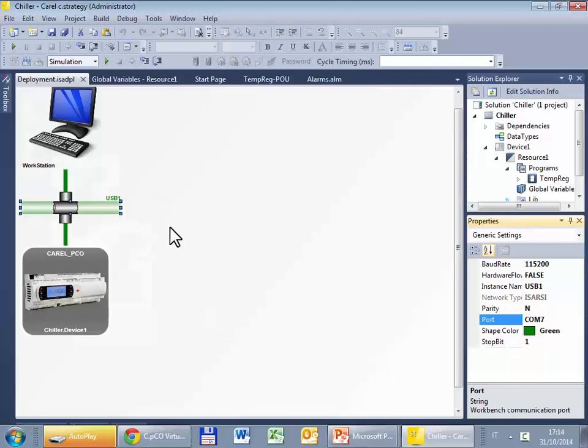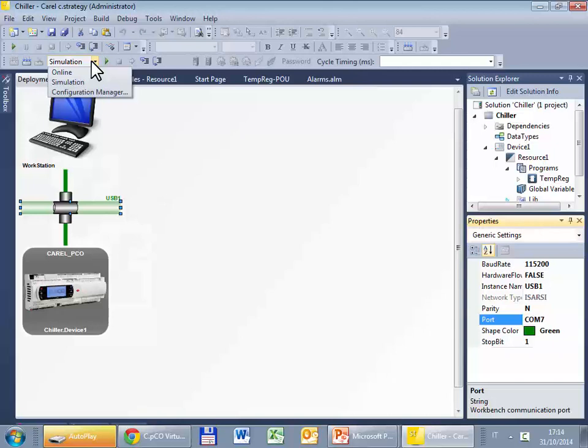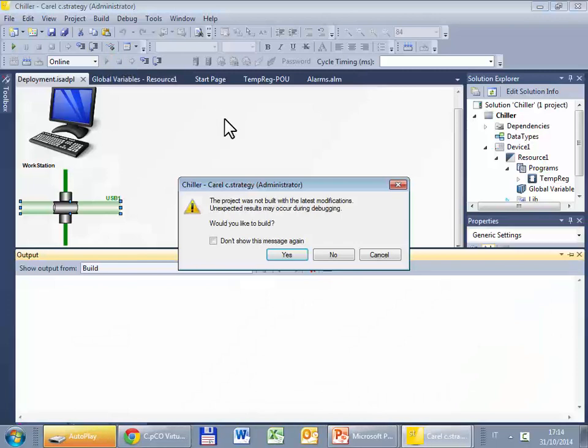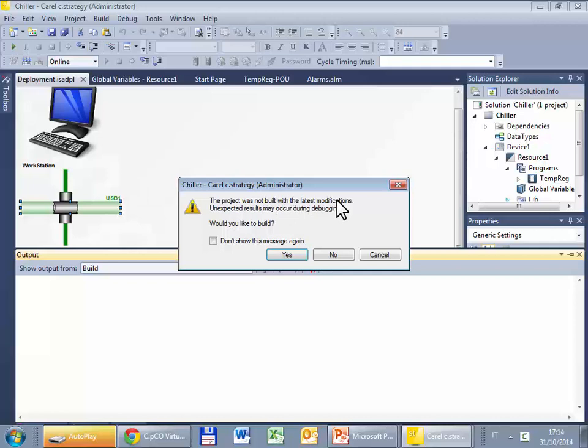Well this time we have to select not simulation but online and then start. This message states that the project was not built with the latest modification. That is the project I have at this moment in the PC is not the same project running in the controller. Because I modified some settings here. So in this case it's better that I download.